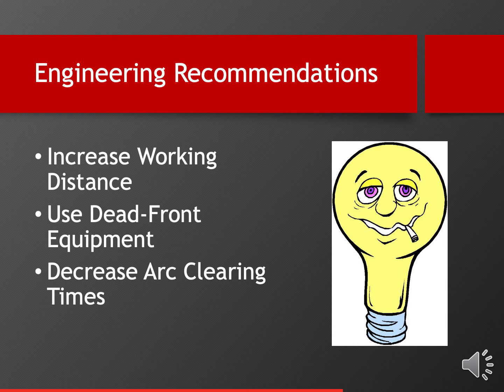The use of dead front equipment, meaning there's a solid barrier between you and the exposed parts at 50 volts AC or more. So we'll talk about what that looks like and some of the limitations of that. And then probably the most important thing we can do from the engineering side is to decrease the arc clearing times. So let's go ahead and jump into this and talk about those issues right now. Let's go to the next slide.